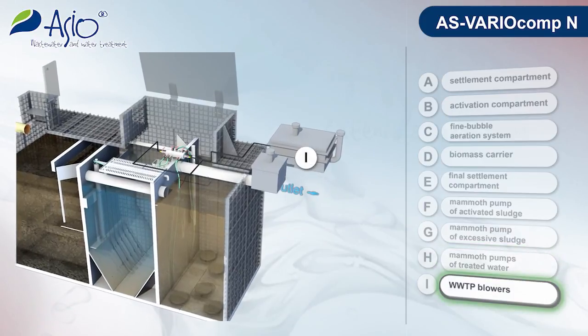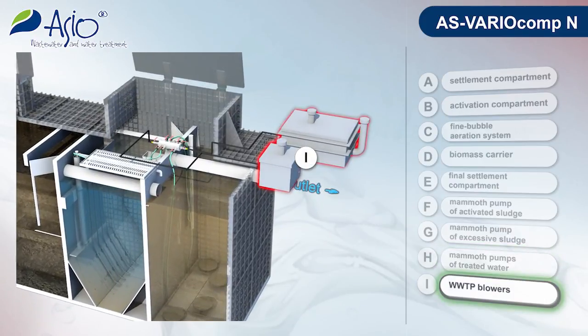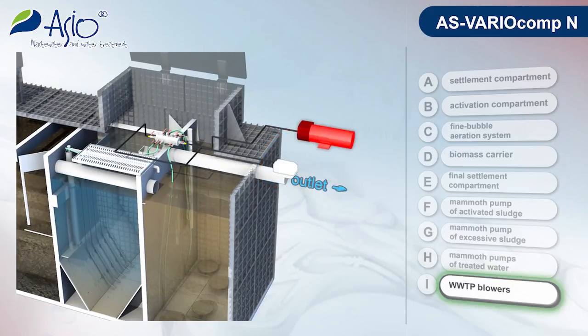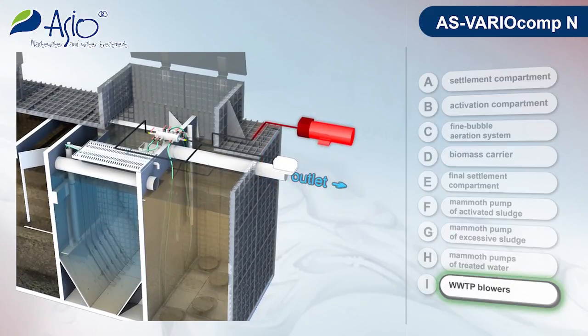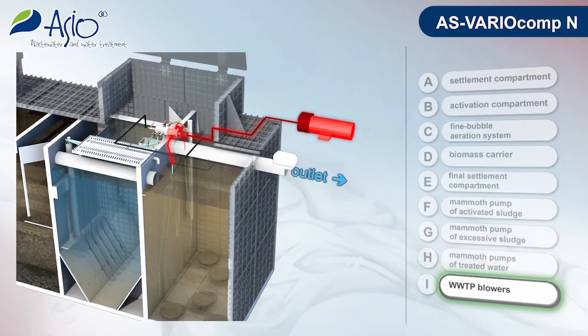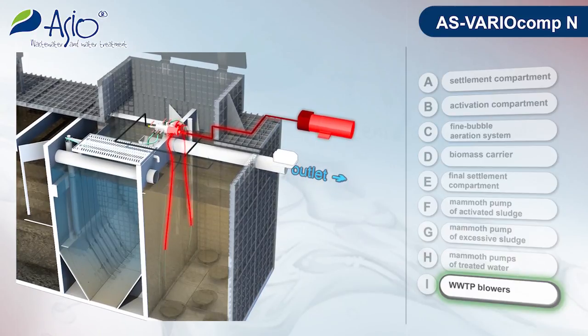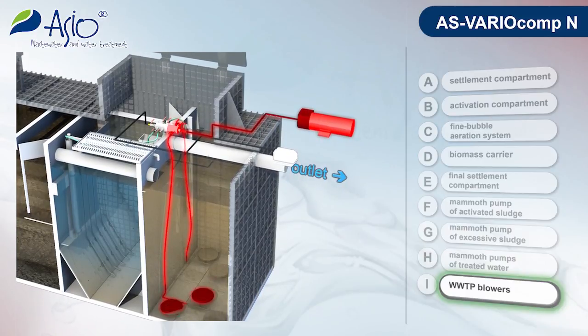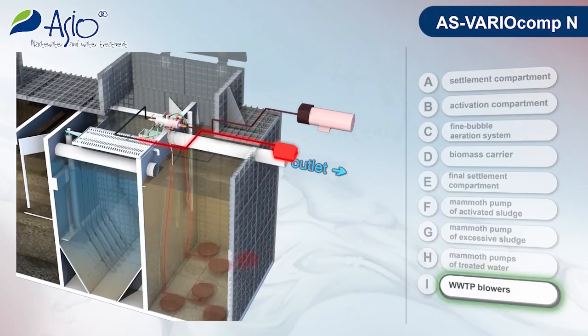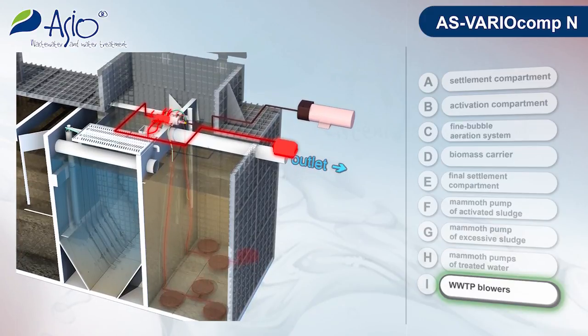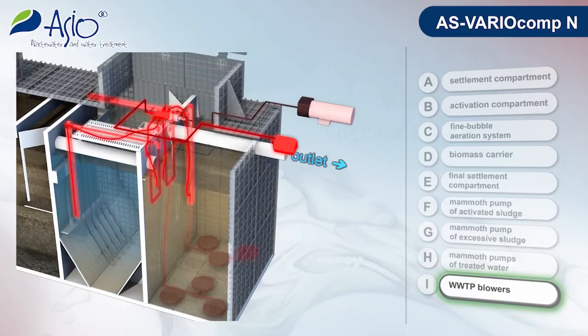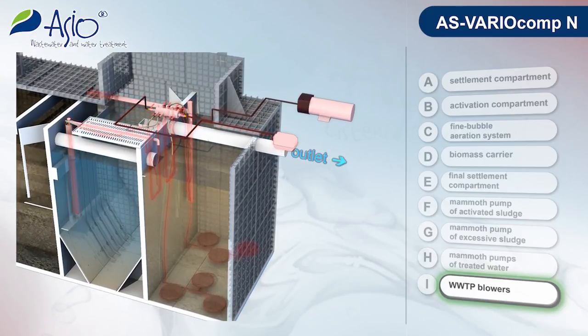Air is fed into the wastewater treatment plant using a pair of blowers. The first blower supplies air to the fine bubble aeration system in the activation part of the plant. The other blower is used to drive the mammoth pumps, making it possible to achieve the optimal setting of the plant.